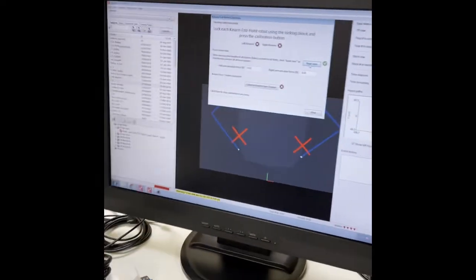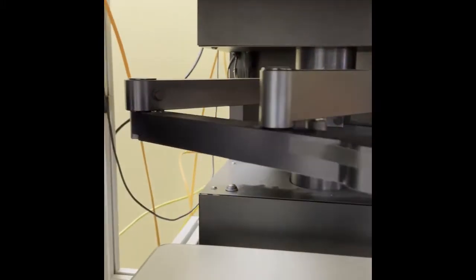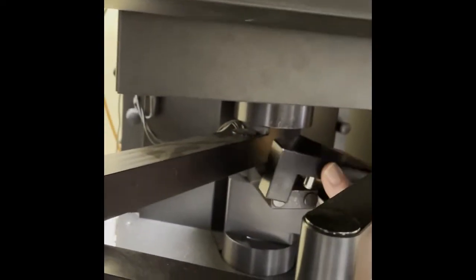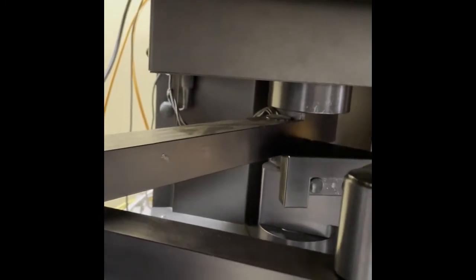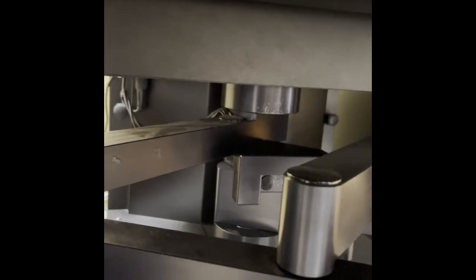So now I'm going to go down in here and need to move the robot in such a way. This is a bit hard to see. There we go. That's where the calibration block needs to go. The calibration block, the arrow points towards the robot. So you want to put that back on there. It might be very difficult to get on. It might be a bit tight if it's a newer Kinarm especially.